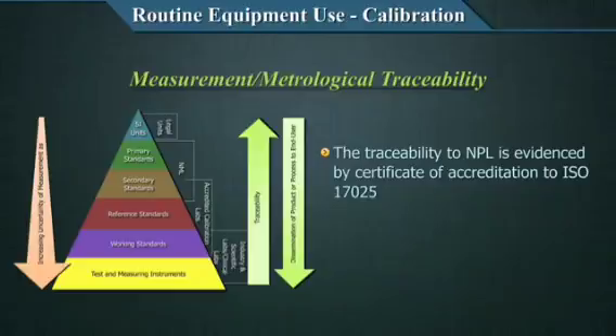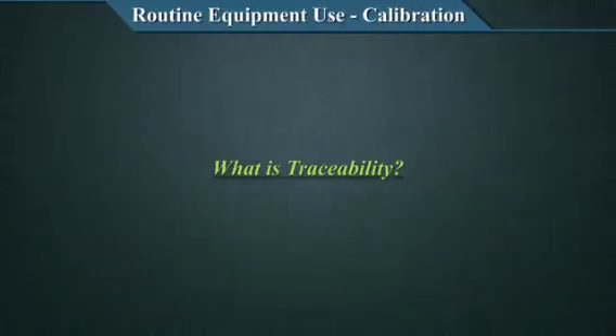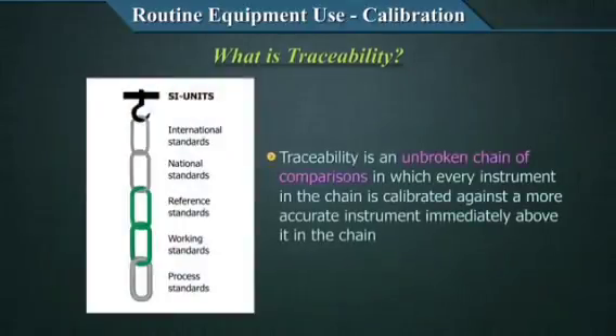To reiterate, as you see here, there is a dissemination of material in a traceable way, but with a certain level of increasing uncertainty. That was just a reiteration of what I said earlier. I hope that concept is fairly clear to you. Once again, since it is a new concept, I would like to reiterate with another illustration. Traceability is an unbroken chain of comparisons. Look at the links in this chain, in which every instrument in the chain is calibrated against a more accurate instrument immediately above it in the chain. Remember the picture from before?